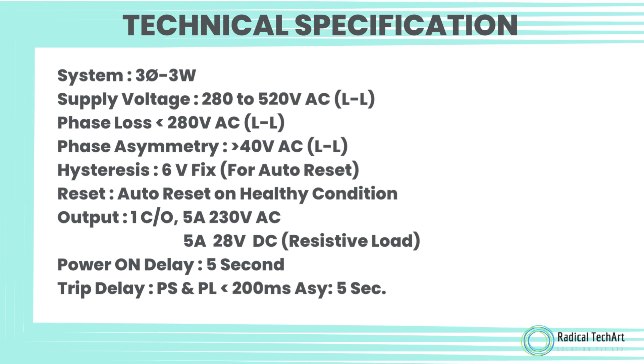Power on delay: 5 seconds. Trip delay: phase sequence and phase loss less than 200 milliseconds; asymmetry: 5 seconds.